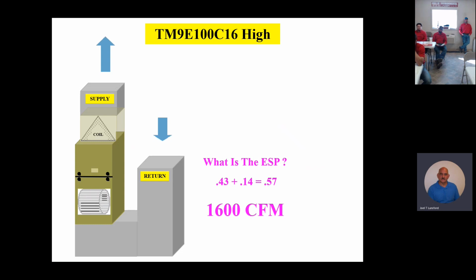From a field application, you don't have to be down into the 2 or 3 CFM range, especially on this particular furnace. That's a 4-ton drive. That 16 means it's a 1600 CFM drive on that furnace. And so if you're 1605 or if you're 1590, you're close enough for all field application. Any questions on that?